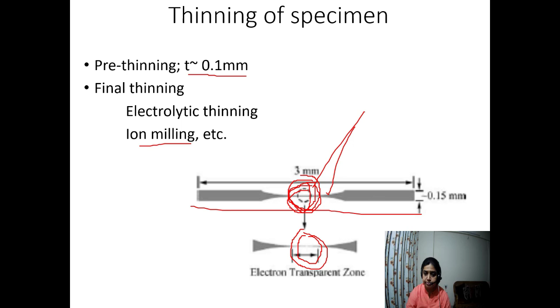So a gallium ion beam is directed towards this region. They take out the material from here, so this area gets very thin. That is the electron transparent zone. This area becomes the electron transparent zone. We cut it and take it to the TEM grid. There again, like in the SEM, we do image formation.